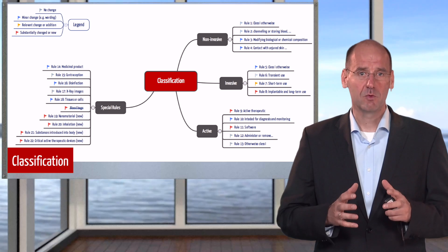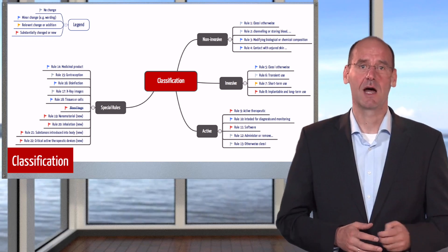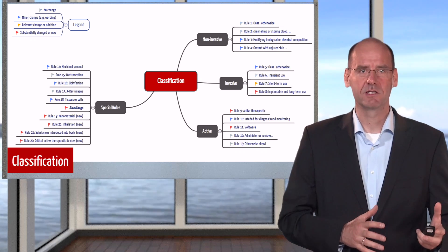Talking about the classes: as already mentioned, there are four classes — 1, 2A, 2B, and 3 — and in a way, class 1 star, which makes it five classes. In contrast to the FDA, there is no database linking products or product types to a certain class. The Medical Device Regulation defines 22 classification rules in Annex VIII. These rules consider the criticality, whether the product is invasive and, if yes, for how long. There are rules for active devices and for devices containing nanomaterials or medicine. If you need any help with classifying your product, just let us know.